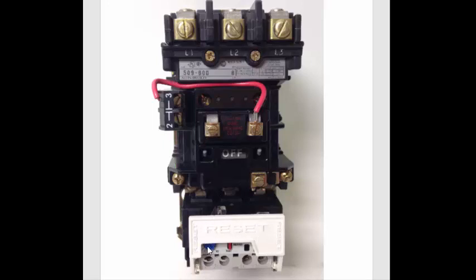The overload relay is adjustable, and it has a reset just in case the phases overheat. The relay will trip and will open up a set of contacts. So we have contacts down here for the overload relay, and at the bottom of the overload relay, we can't see it from this angle, but the three phases would then go out to the motor.